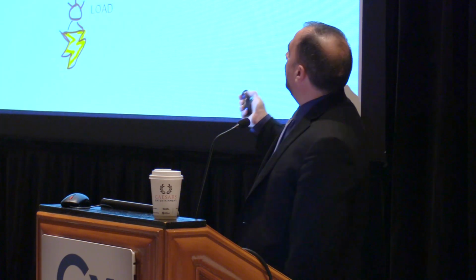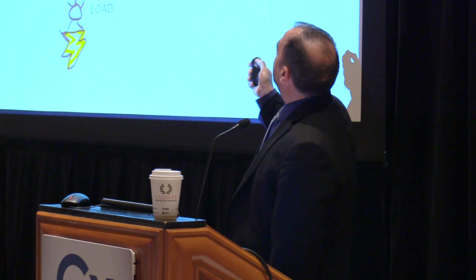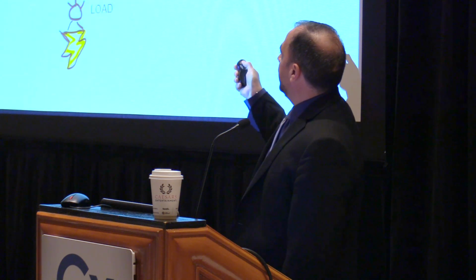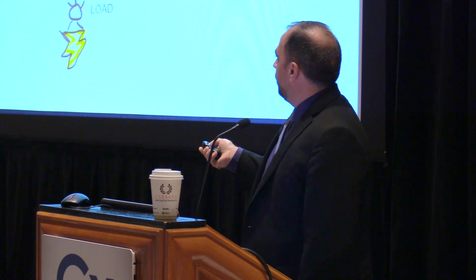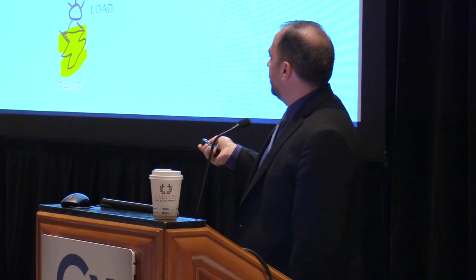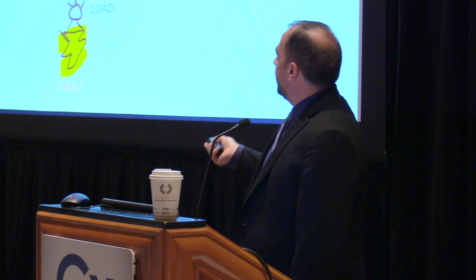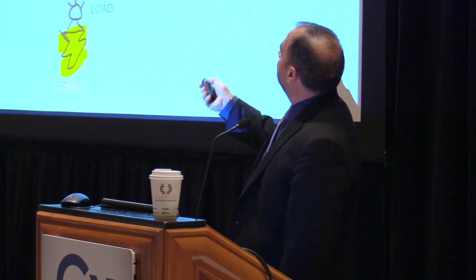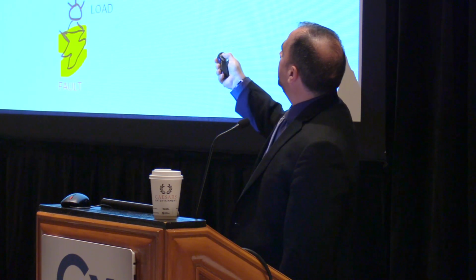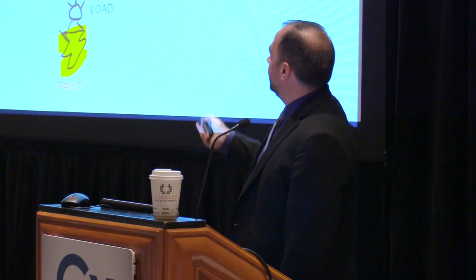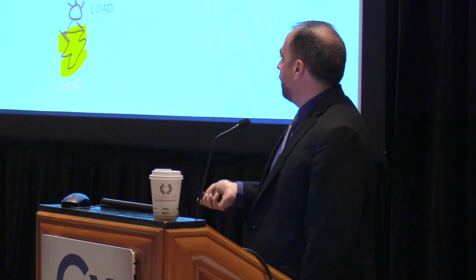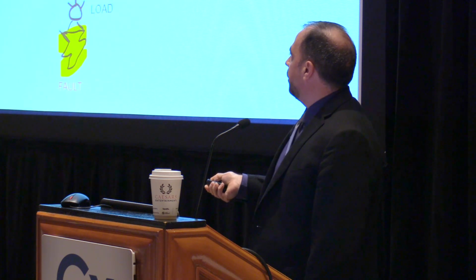In the other case, where we have a non-separately derived system, we don't have that bond here anymore. We want to have a 3-pole switch. This would be the right place to have a 3-pole switch, because if we had a fault here, there's no connection between these two, so that's good. So the fault goes that way. If we had a 4-pole switch in that system, we'd have what's called a floating neutral, which can cause all kinds of problems on your system, overvoltages and other problems.